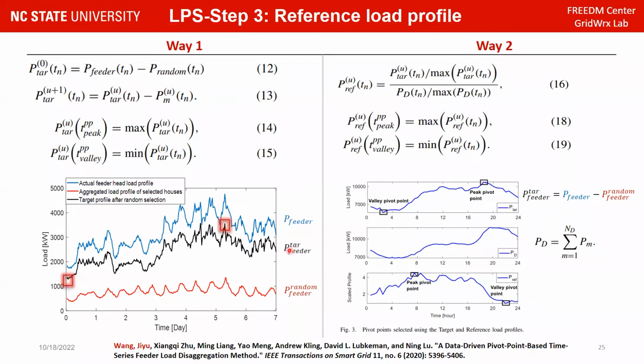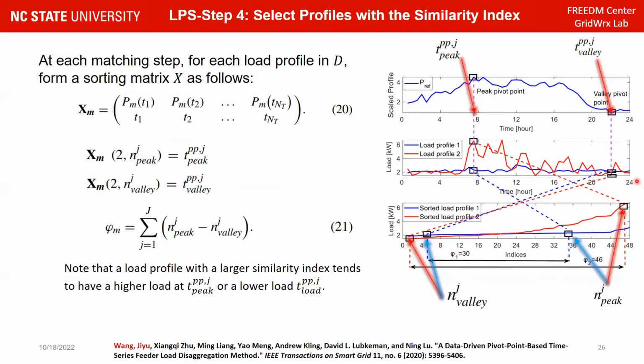So a simple way of doing that is, based on the target feeder profile, to select another load profile that peaks at this period and then has a valley around some area. And then the second one is more targeted selection. If there are two curves that both peak at the same time, which one should we select? We select based on similarity, meaning we use the peak to select here, and then our valley is here. Then we select a curve that has the closest shape, like the distance between peak and valley. That way we guarantee that our selected curve will have a better characteristic overall to match the overall curve shape. Instead of having a peak here and a valley here, that kind of load profile is definitely not as good as the red one, where we have the peak here and then the valley there. And that's one way of doing that.